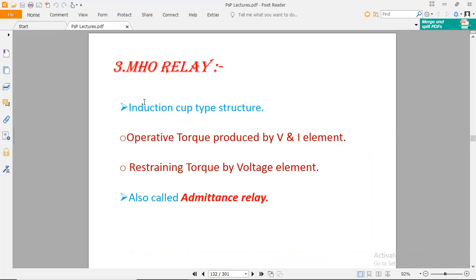Further, the third category of distance relay is the Mho relay. The opposite of Ohm is called the concept of the Mho relay. It has an induction cup type structure. Operative torque is produced by the voltage and current elements, and restraining torque by the voltage element. It is also called the admittance relay, which is the reciprocal of impedance.